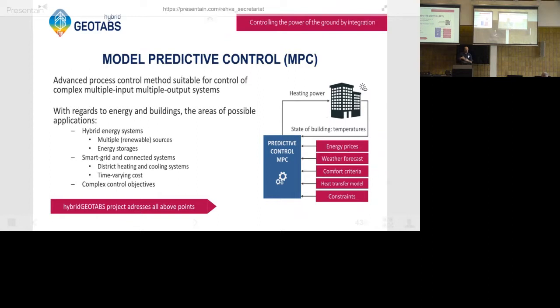If we know that it will, for example, be a sunny day in a transition period, the MPC knows that it might not be necessary to heat up the building, because in a couple of hours some people will come, produce internal gains, and it will be sunny, so heating would be the control action a regular controller would take, but that's not good, and MPC doesn't do that. MPC basically anticipates control actions based on all these parameters, and it can also include constraints, for example that we want the supply temperature to be only 40 degrees, or similar things.